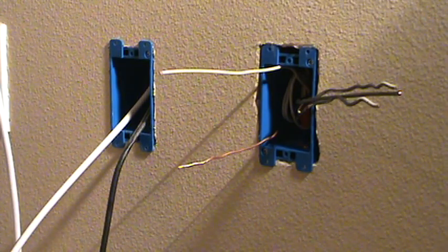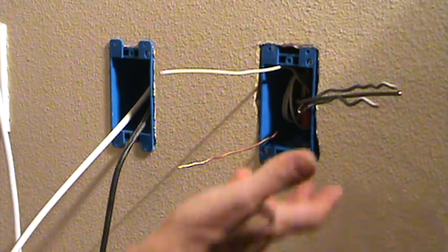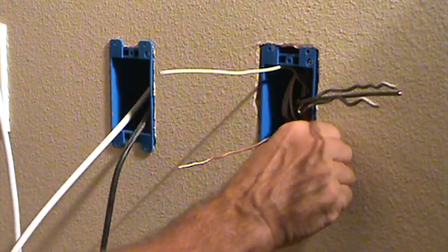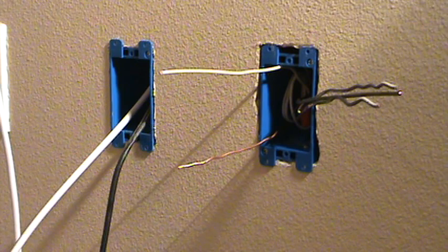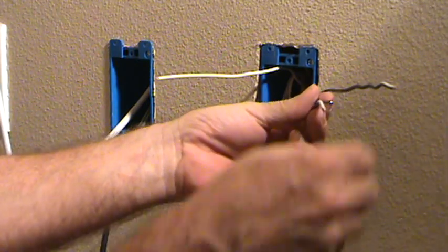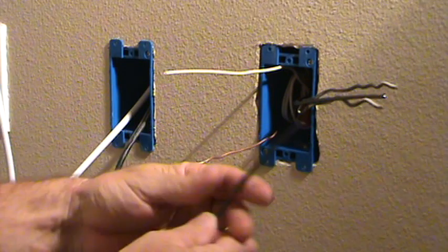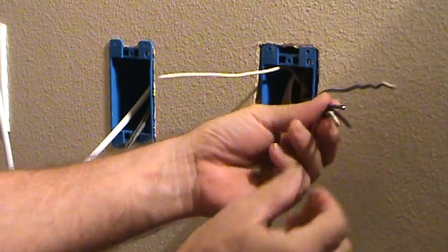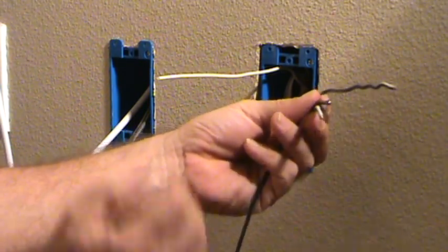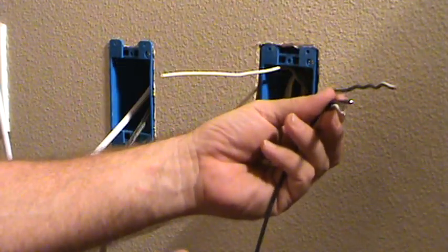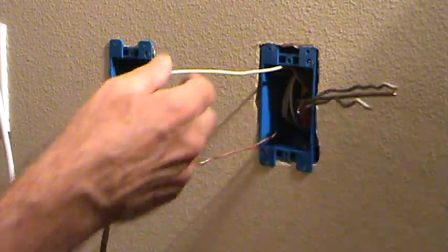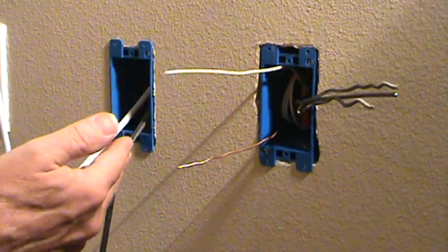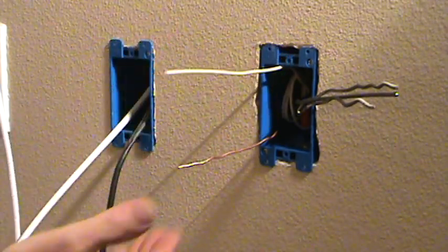Now here's something else I could have done. There's different ways to wire up boxes like this. This is just a standard box. Now I could have taken just two wires and put a pigtail on it, maybe got a yellow wire nut on there, push that back in the box, then I only have two black wires coming out. And I could have done that on the white and only had two white wires coming out instead of one.